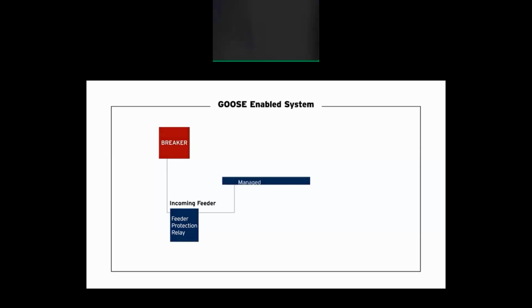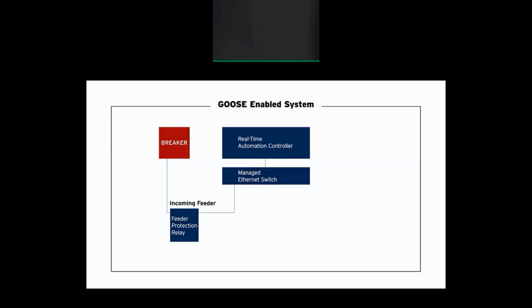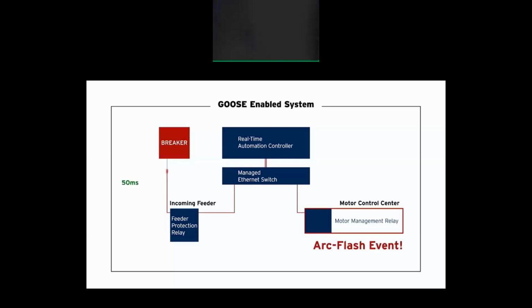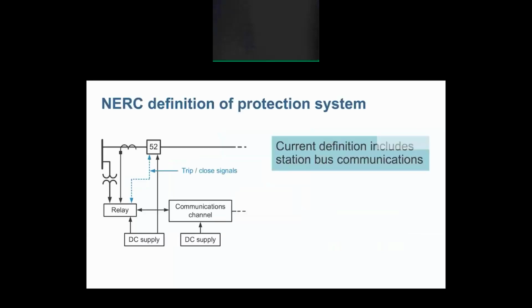This test was done with a digital trip circuit. The relay opens the breaker to stop the flow of energy into the fault when it gets a trip message from the device that detects the fault. And in this case, that trip command travels as an Ethernet message through an OT Ethernet network to trip the breaker.